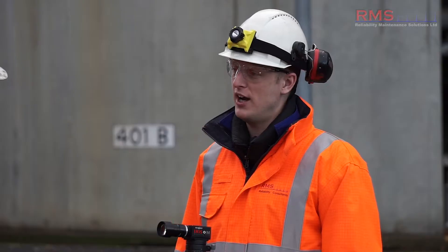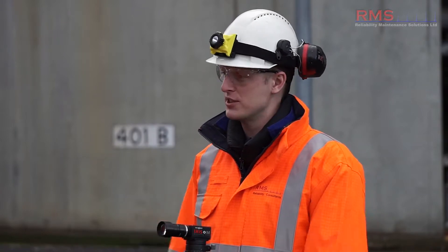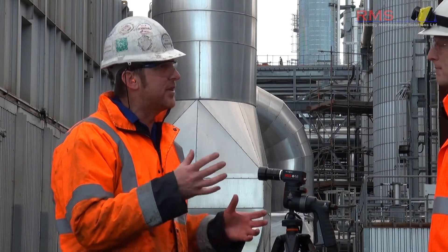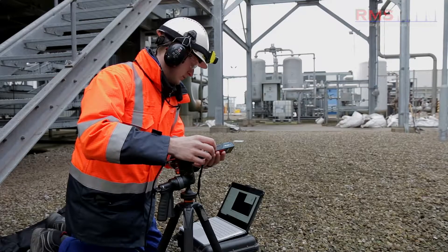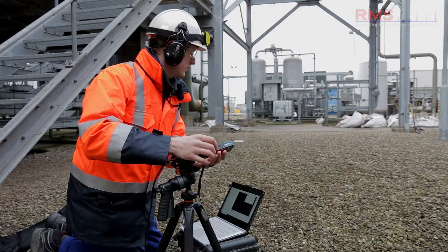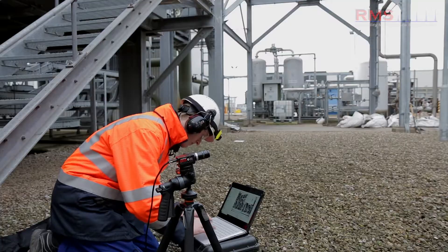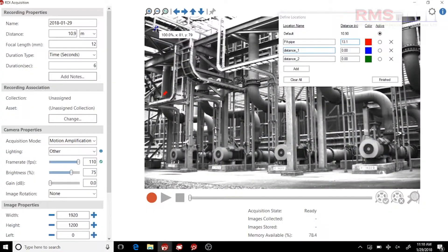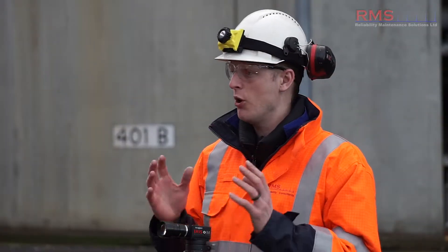Yes, it's the same as having an accelerometer — spot on. But we do need to set the distance; there's a bit of setup involved. You need to put points on there and take the measurements for those points, so you always get the right amplitude. The frequency is always correct when you take the measurements.